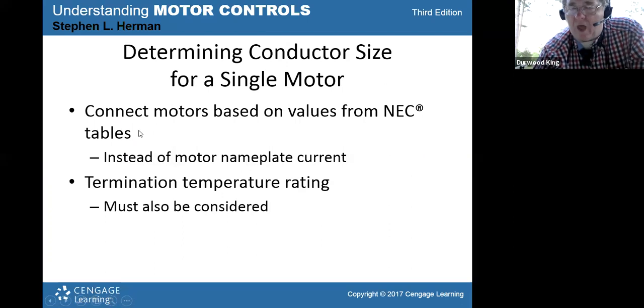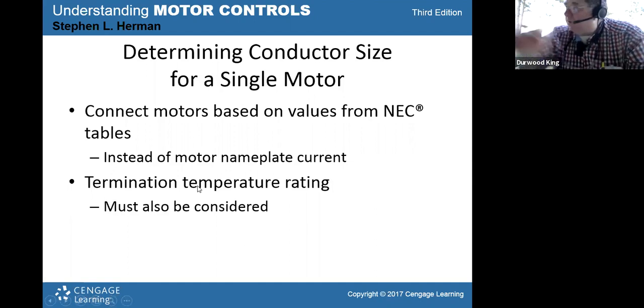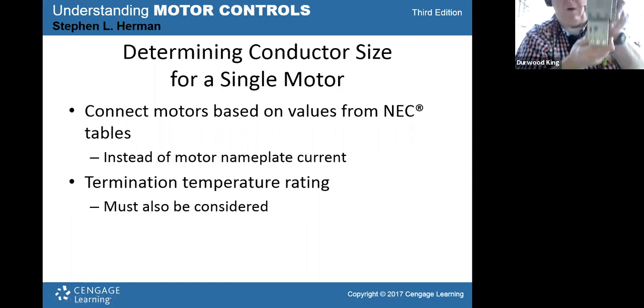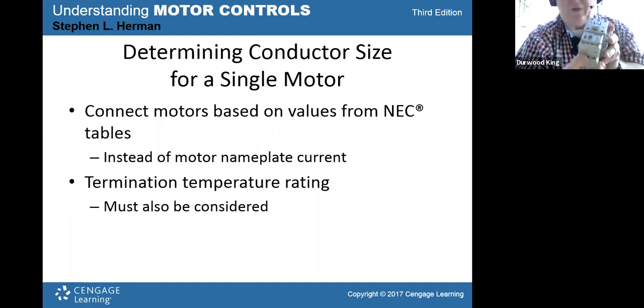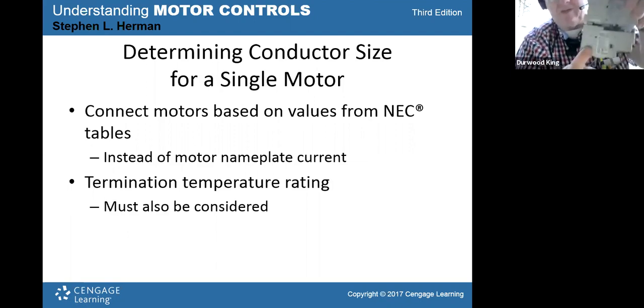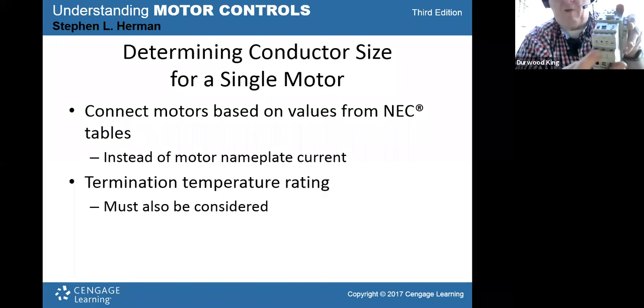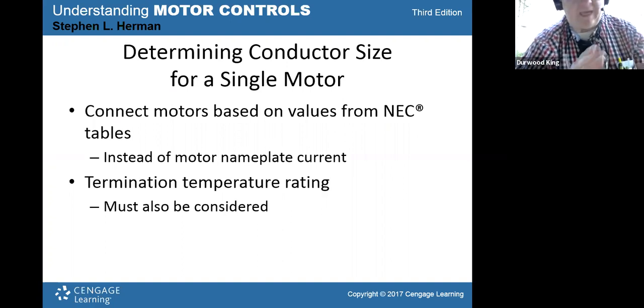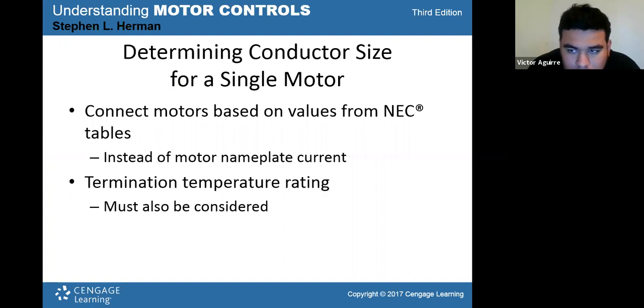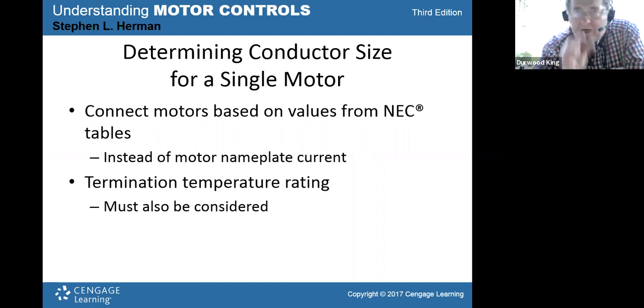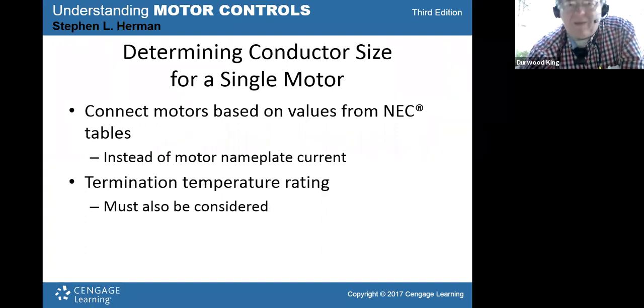So you're going to go off of the chart that we just looked at to get the amps for the motor when you pick the wire size. And you also have to consider the temperature rating of the terminals that you tie to. So what we mean by that is this. You see that starter there? The terminals that you tie to down here, your lugs, there'll be a temperature rating on those, and it's actually stated on the side here. This one is rated at 75 degrees Celsius. The terminals have a maximum rating of 75 degrees Celsius. You have to keep that in mind when you pick the wire size, and we're going to see really shortly where that matters.